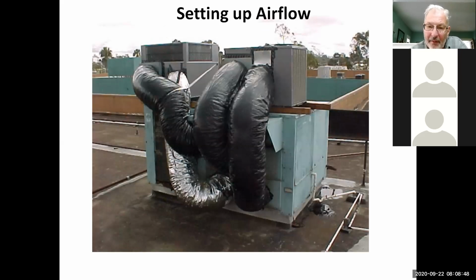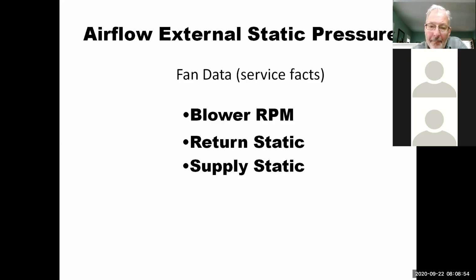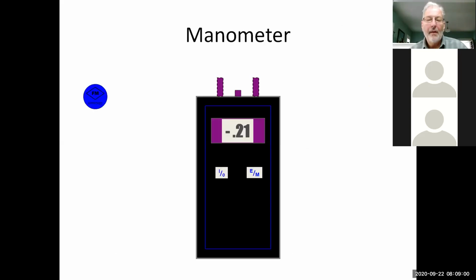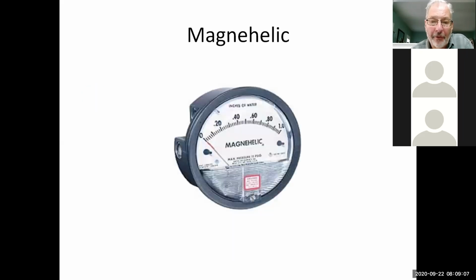Okay, so we're going to talk a little bit about airflow because airflow setup's a little different on our units. So we're going to review belt drive airflow, and then we're going to take a look at some of the direct drive airflow. Now, in order to get the proper airflow, you've got to have a manometer. We've got to know what the static pressure is on the system. Electronic manometer, magnehelic, whatever you guys use is kind of up to you, whatever you're comfortable with.